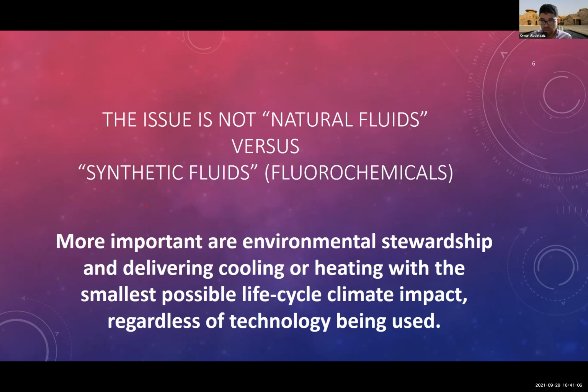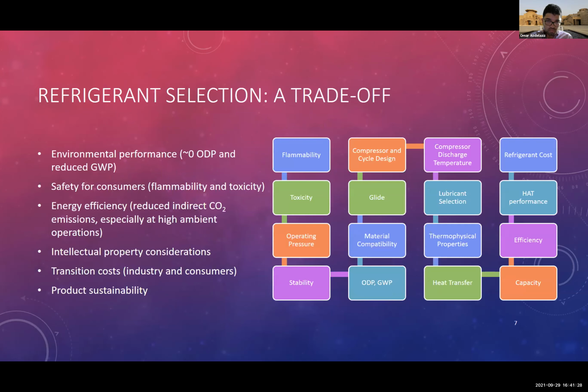So the issue is not natural fluids versus synthetic fluids. The issue is more the environmental stewardship and delivering cooling or heating with the smallest possible life cycle climate impact. We don't need to worry whether it's a natural refrigerant or a synthetic refrigerant. We just want to make sure that we are not impacting our environment. So how can we do it? It's a trade-off. There is what we call environmental performance. We want zero ODP, or as close to zero as possible, with low GWP, or what we call reduced GWP. It has to be safe to the consumer and energy efficient. That is important to reduce the indirect CO2, because this is the amount of emissions that happens along the life of the equipment. We need to understand the intellectual property considerations.